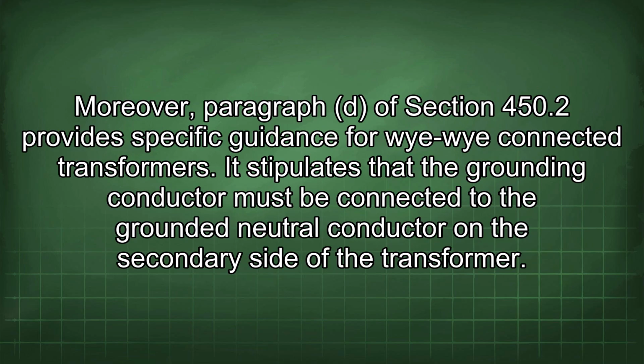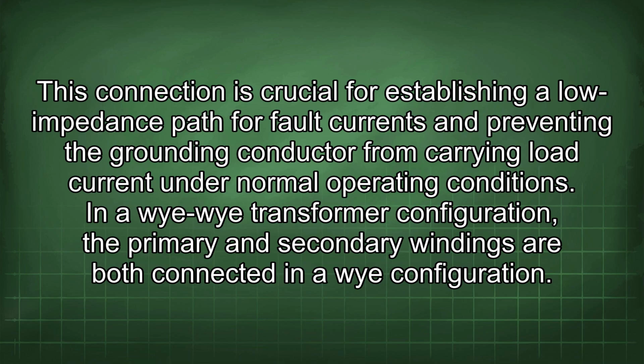Moreover, Paragraph D of Section 450.2 provides specific guidance for Wye-Wye connected transformers. It stipulates that the grounding conductor must be connected to the grounded neutral conductor on the secondary side of the transformer. This connection is crucial for establishing a low impedance path for fault currents and preventing the grounding conductor from carrying load current under normal operating conditions.